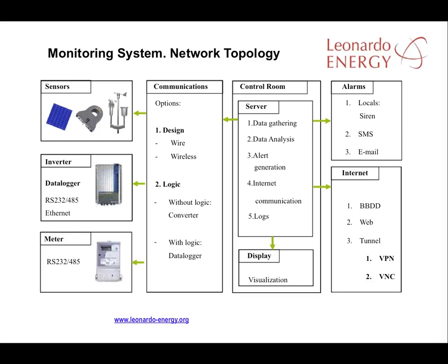Here we have the topology of a monitoring system. The different inputs might be sensors, inverters, or the meter. The communications port that is usually used with the inverter is an RS-232 or RS-485. An RS-485 is also normally used with a meter. Newer meters also support an internet connection. You will have a choice between wireless and wired connections. Normally wired connections are recommended because they offer greater reliability.